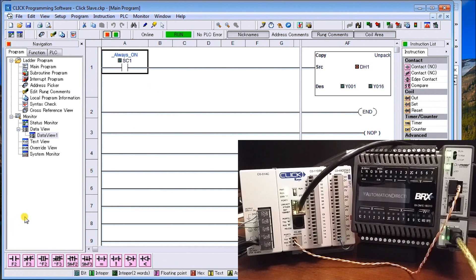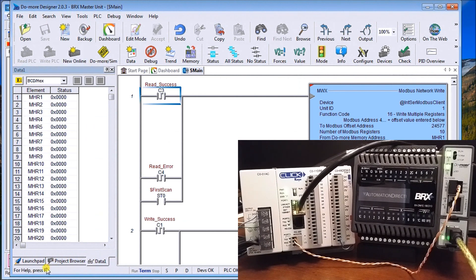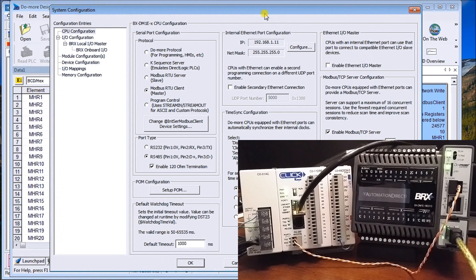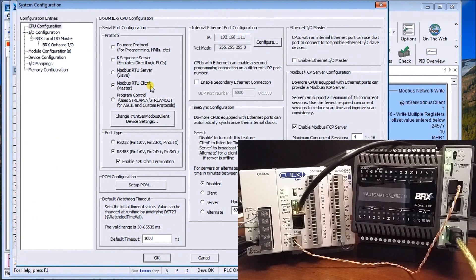Now let's go over to our BRX PLC software. Under Configure and the configuration settings, you'll notice the serial port configuration shows Modbus RTU Client — which is our master — controlling communication out to the Click. Under port type we have RS485, and we've enabled the 120-ohm termination resistance.